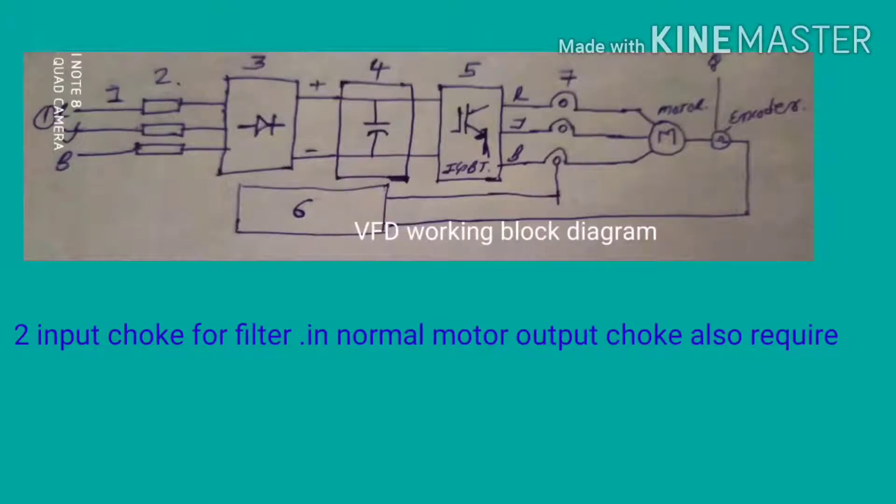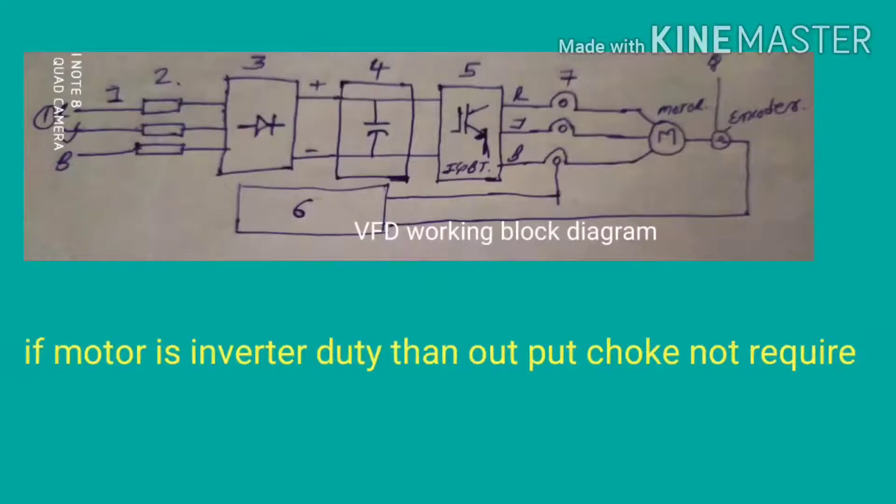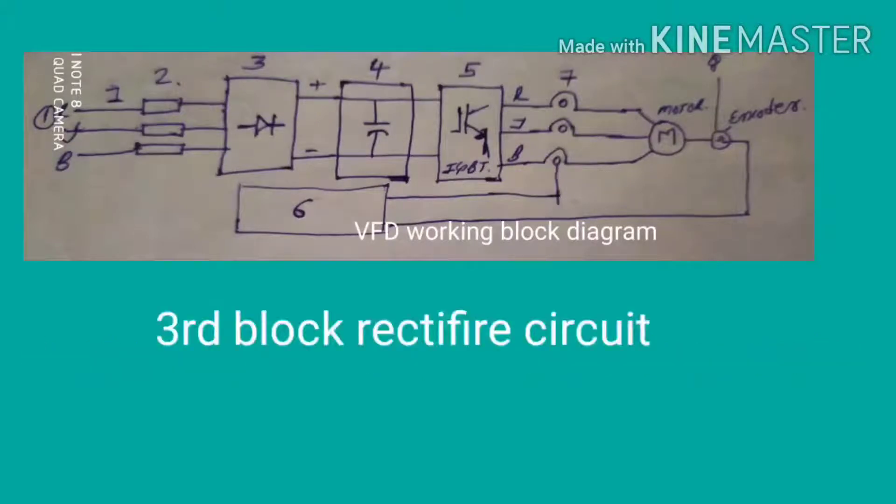But if the motor is inverter duty, the output choke is not required. However, if the motor distance and VFD distance is more than some meters, then the output choke is also installed at the output side of the VFD.